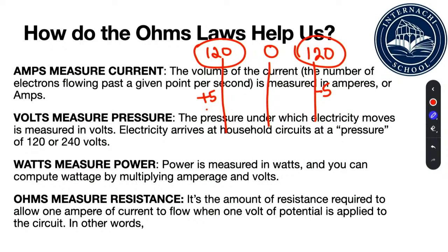When I take positive 5 and add negative 5 to it, I'll end up having 0. That's why on central air conditioning systems, electric radiant baseboard heat, as long as it doesn't have an outlet built into it, and on well pumps, many times they won't even have a neutral wire. They'll only have 2 energized conductors. The reasoning is, if there's no amperage flowing on that conductor, I don't even need it. That's true, but it doesn't really count when dealing with electric dryers or electric stoves, because those have little light bulbs in them.